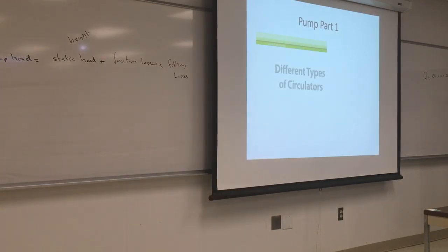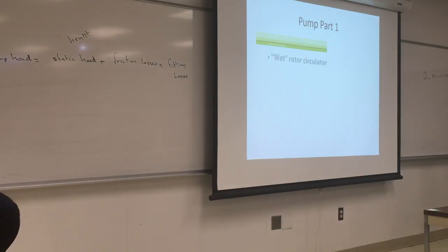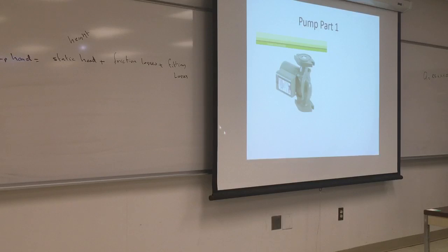Okay, now that we're clear that pumps and circulators are different things, there are also several different types of circulators, each with its own design and best applications. Some are wet rotor, some are dry. These dry circulators are also referred to as close-coupled or three-piece circulators, by the way. Some need to be lubricated, others are self-lubricating. Some are fast, some run slow, while others can even vary their speed from fast to slow. In this course, however, we're going to focus on wet rotor circulators, and we'll use the Taco family of double O cartridge circulators as the great example of this type.